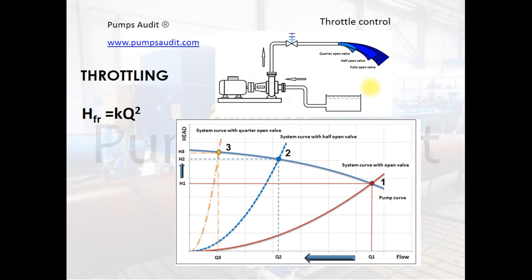Throttle control is the method of changing pump flow by increasing or decreasing the resistance of the pumping system. The resistance of the pumping system is regulated by the valve installed in the discharge pipeline. If we need to reduce the flow, we begin to close the valve. The pumping system curve changes its shape and gets steeper and steeper — we increase the coefficient of losses in this formula.